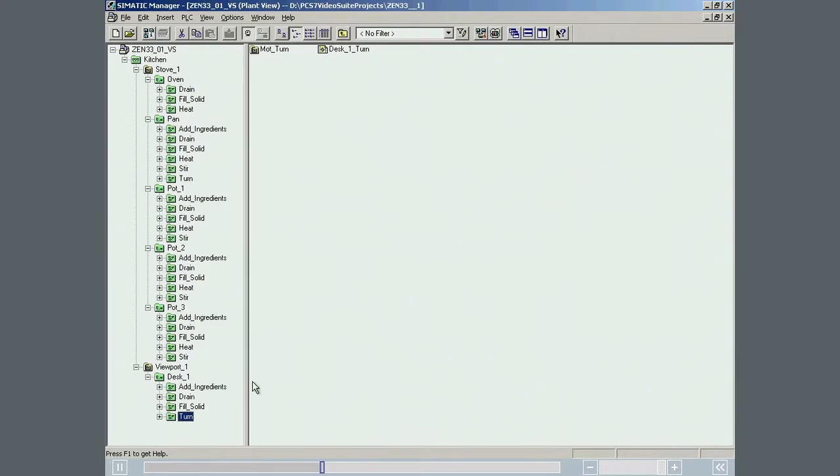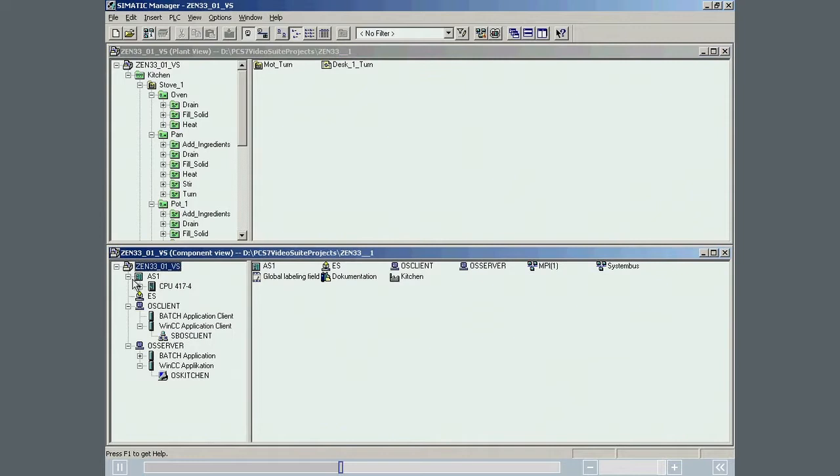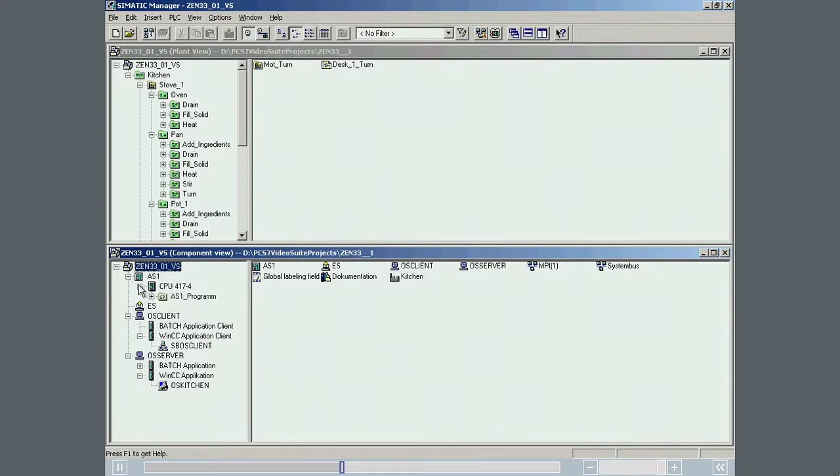In the next step, the SFC types that are already created in Simatic Manager are defined as Equipment Phases for use in Simatic Batch. This assignment is made in the Component view. The Properties dialog of each SFC type is opened and the Category Equipment phase, or EPH, is set.